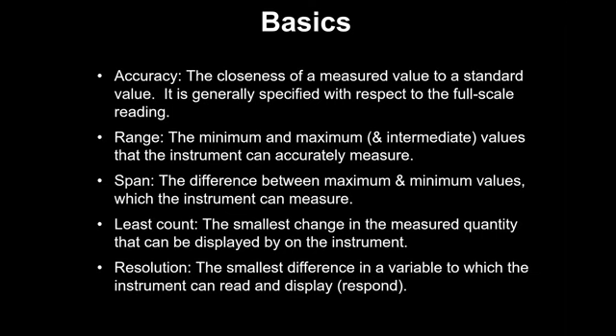The third part is the least count. The smallest value that can be displayed is the least count. Say, for example, we are using a digital temperature indicator having a 0 to 600 range. It will display 1 degree as a minimum. That is the least count of the instrument. It will not display anything less than 1 degree. If it goes to 1.5 degrees, it will go to 2, maybe, or it may be 1 only, depending on how it is configured. But it cannot display any decimal value.